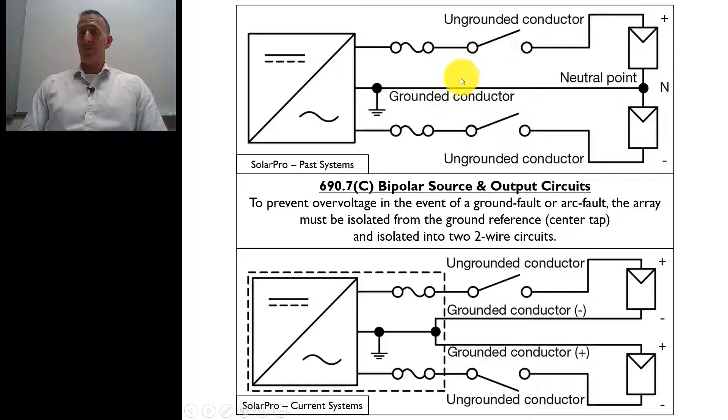And if they ever had a fault and something was lifted, that was no longer connected to the earth. And then that meant that the voltage would actually be the combination between positive and negative, which would exceed the rating of the inverter, damage the inverter, actually cause a safety hazard.